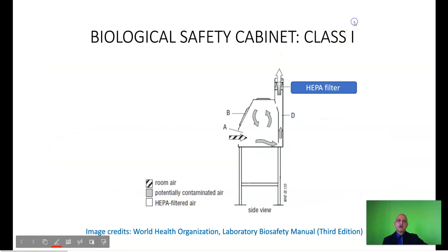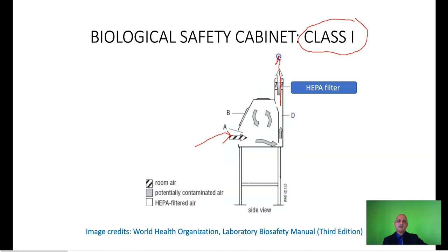Okay, this is a class 1 biological safety cabinet. A class 1 biological safety cabinet is basically a workspace in which you will note the air enters from the outside space and is exhausted through a HEPA filter into the environment. Now this duct may lead outside the laboratory into the external environment, or in some cases it may lead back into the workspace. However, it is recommended that it lead to the external environment. The operator will stand in front of this safety cabinet operating this instrument over here, and he or she will work within the confines of this space. The air circulates within this space, and a major component of the air is exhausted into the external environment via a HEPA filter. This is the basic level of protection to the operator.